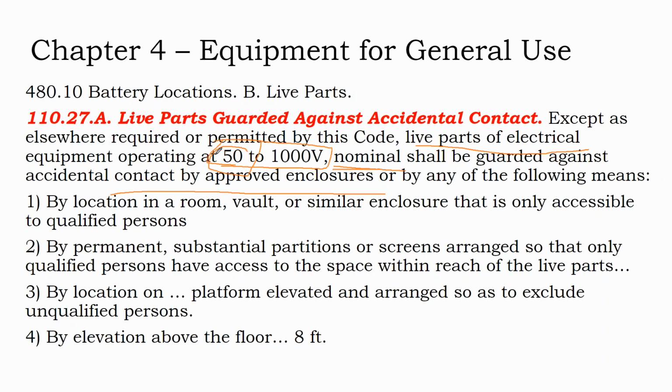So I've walked into a 48-volt battery bank where this project actually did not get off the ground because the installer sold him an inverter that was too large for the battery. It would have discharged the battery way too fast. At any rate, they just had the 48-volt battery bank hanging out on a shelf in the garage. It's like, well, what is that? Well, that's where we're going to get into after the break, talking about where the code is driving for self-assembled battery banks versus pre-assembled battery banks.